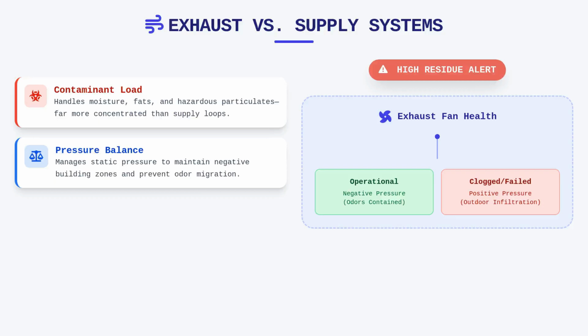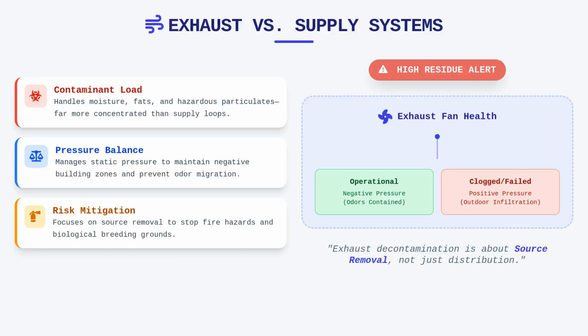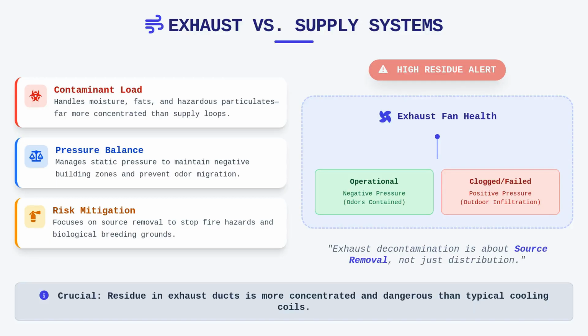Unlike supply systems where we worry about distributing clean air, exhaust decontamination is primarily about source removal to prevent the accumulation of hazardous particulates that could facilitate fire or create a breeding ground for biological contaminants. You must approach these ducts with the understanding that the residue inside is often more concentrated and potentially more dangerous than what you would find in a typical cooling coil or supply duct.